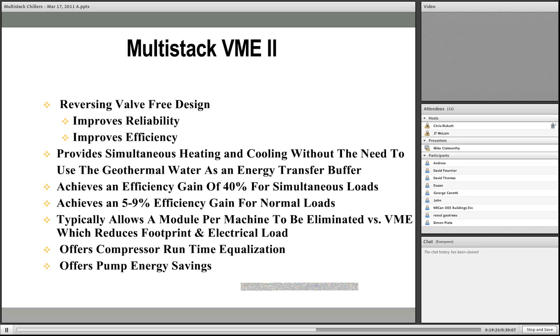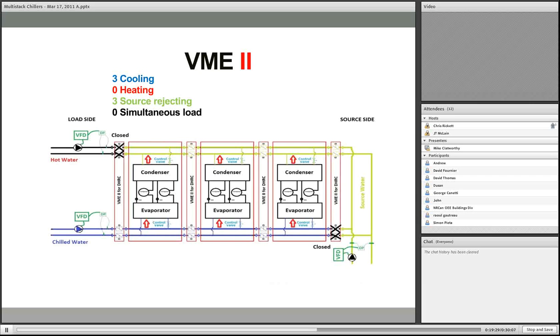And by doing VME2, we were able to eliminate a reversing valve and maintain counterflow in our heat exchangers, and also to have a smaller electrical footprint. But let's take a look, and these are all top views of a water-to-water heat pump system. In the diagram, or the legend at the top, it shows what each module is doing, and the secret to this application is closing the right set of valves. So this is a set of valves, this is a set of valves, valves here, and so on. And by closing the right set of valves, I can reconfigure the system on the fly and maximize my efficiency.